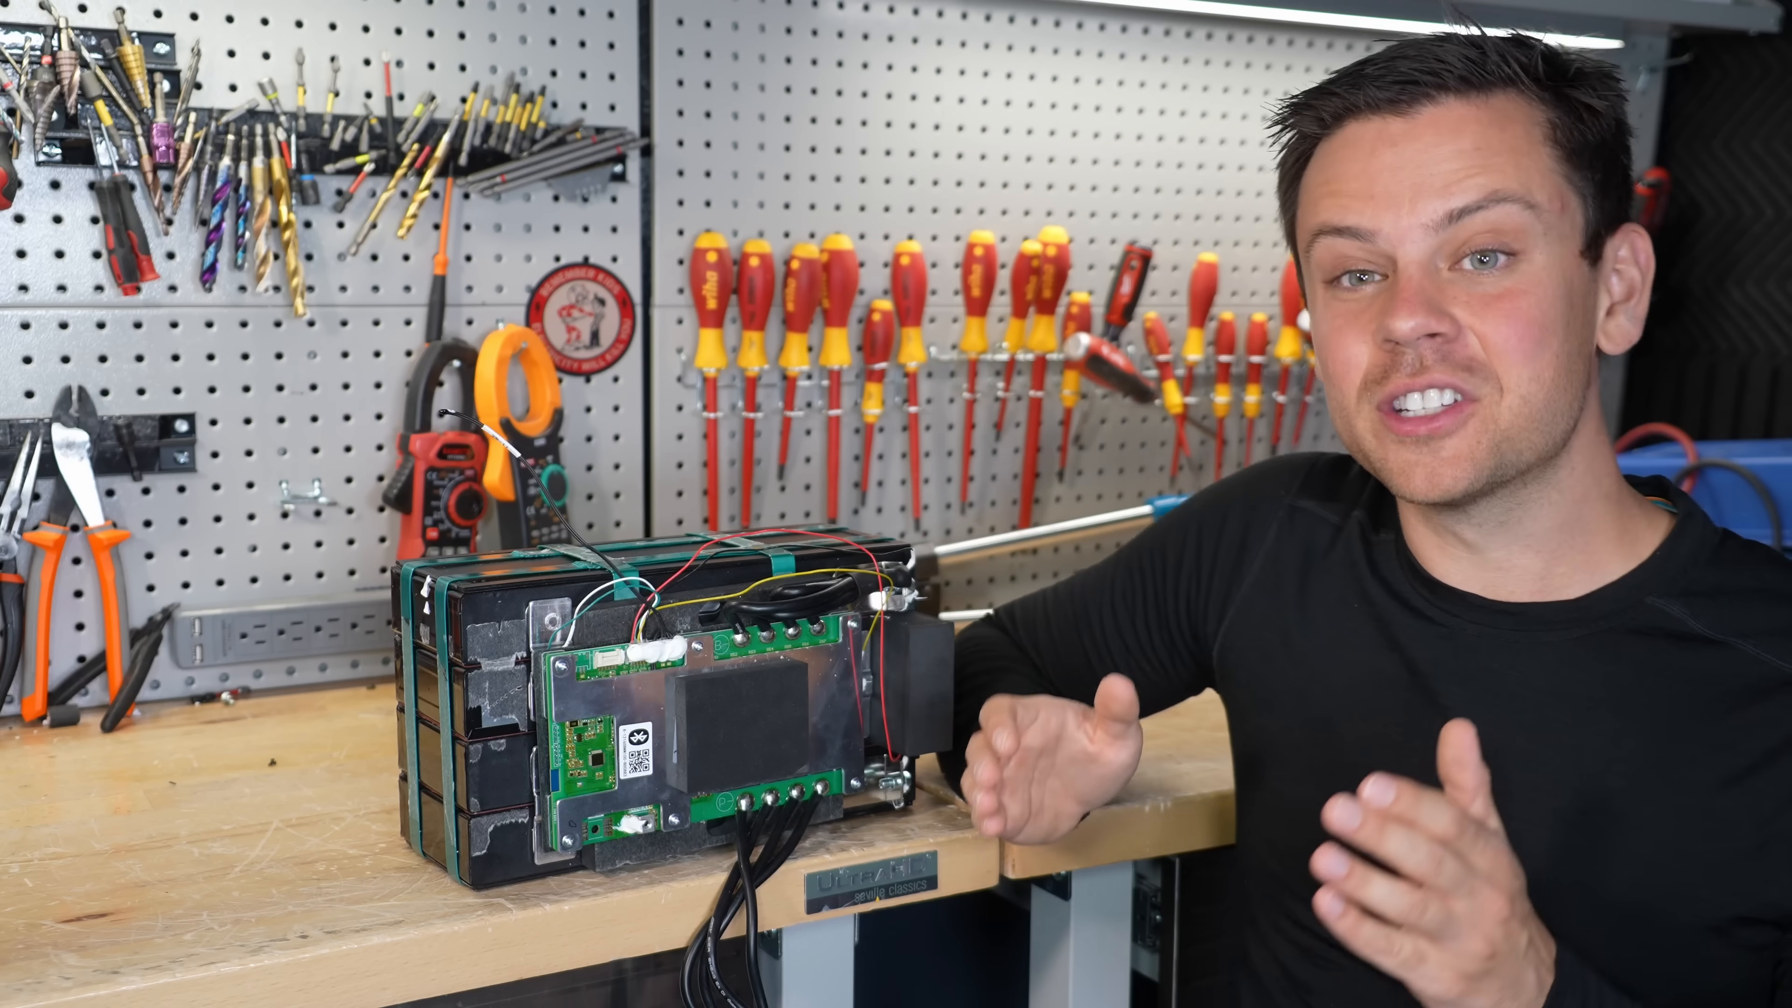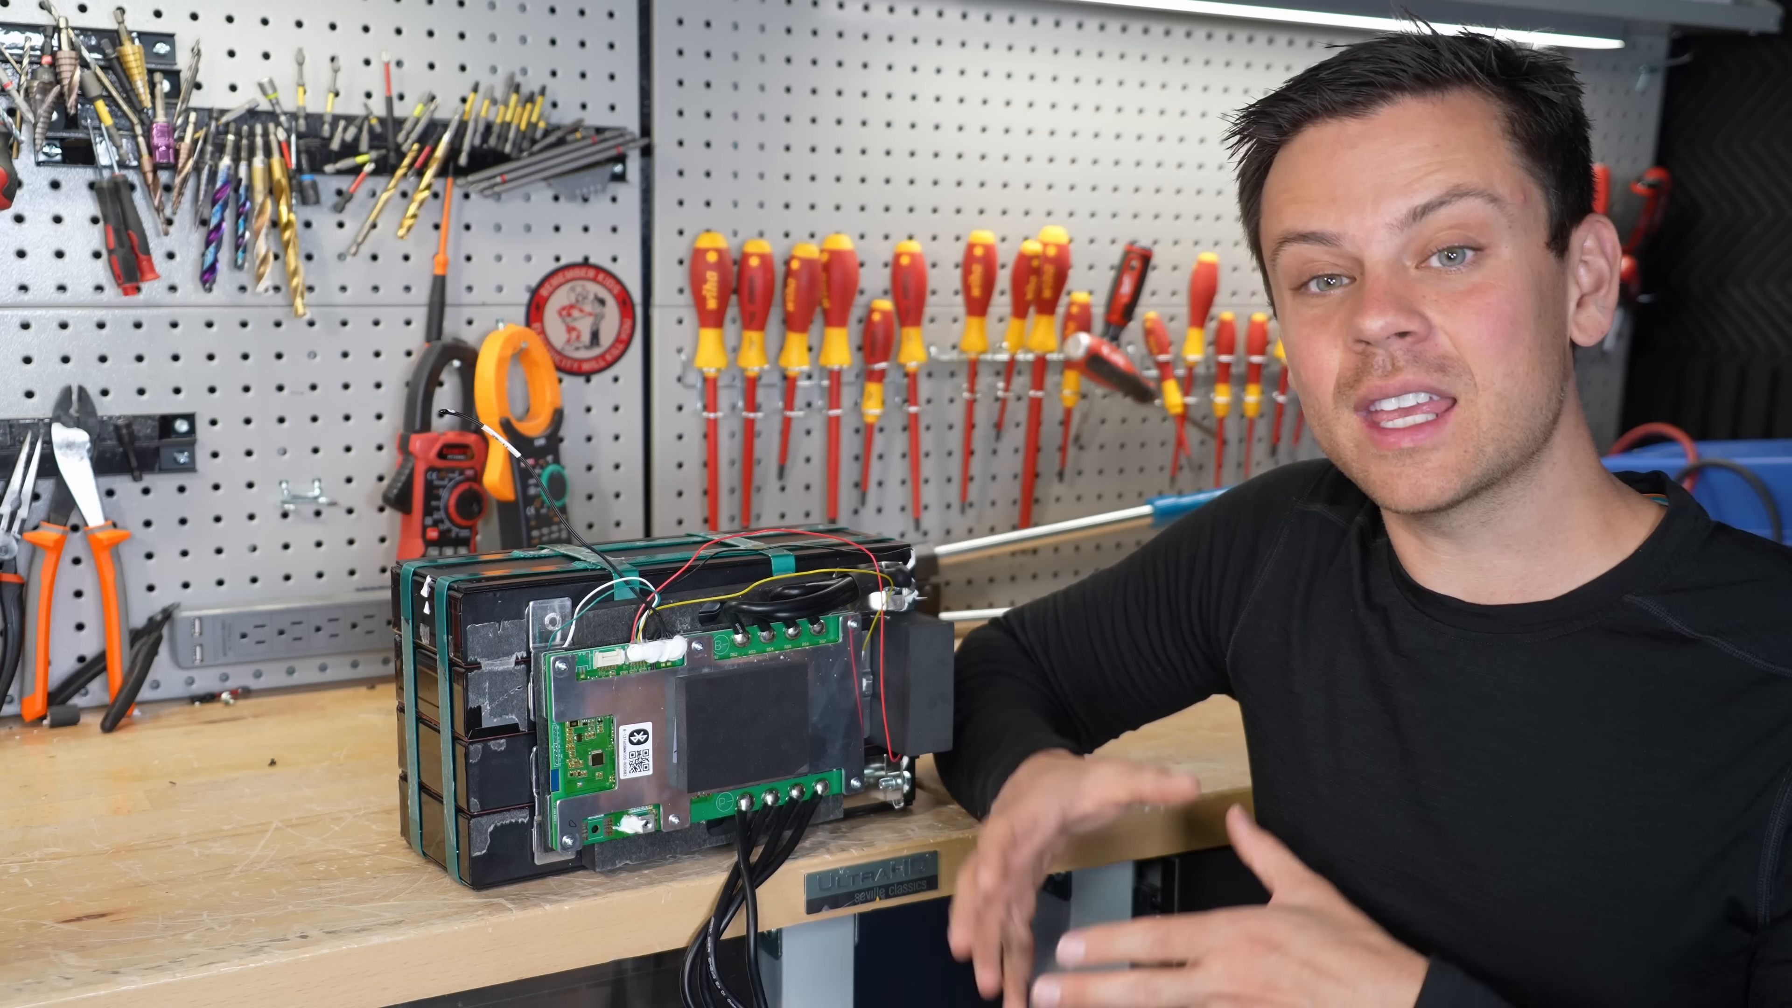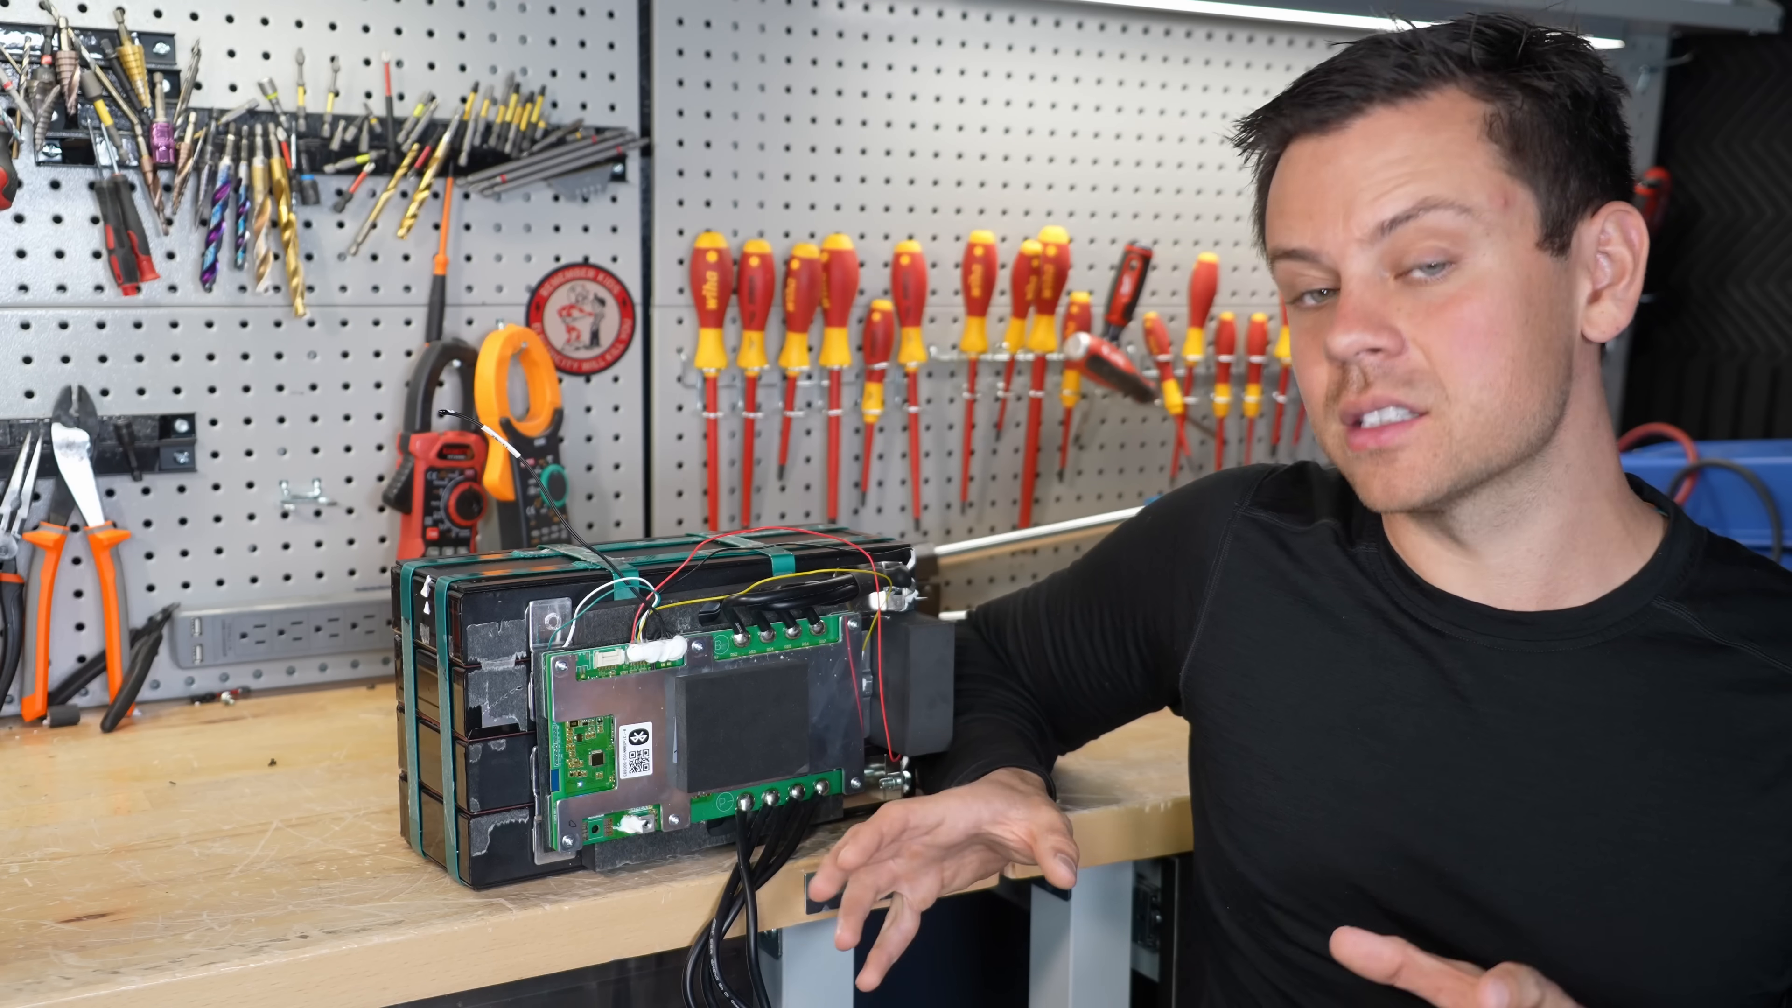Let's say you don't tighten down the main terminals properly. Those bad connections can heat up and they can melt terminals or they can get so hot that they can catch something else on fire next to your system. And that is a very common failure mechanism.